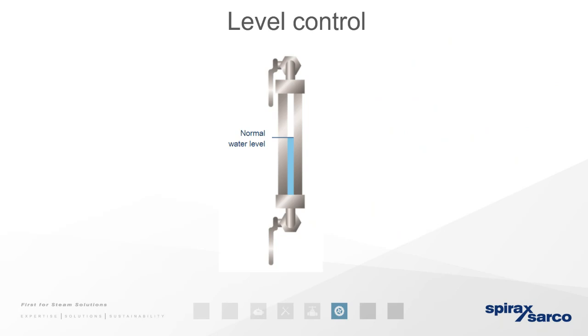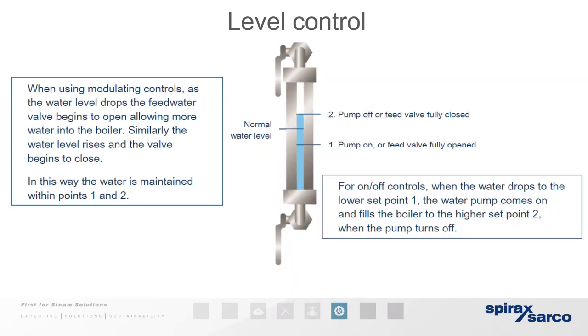So we'll start off using the gauge glass to demonstrate how rising and falling water level during various stages of steaming can affect boiler operation. And hopefully you can understand why we need the control. Here there are likely to be a number of visual level markers on the level gauge. You'll have your normal level, your pump off point if it's on-off control, and your pump on point. If the boiler is fitted with on-off pump controls, then there will be a switching mechanism to turn the pumps on and off.